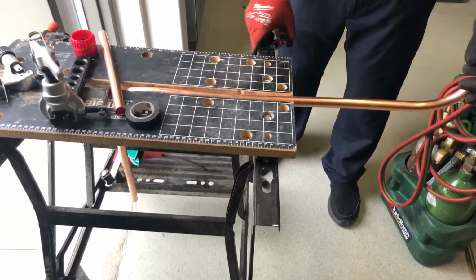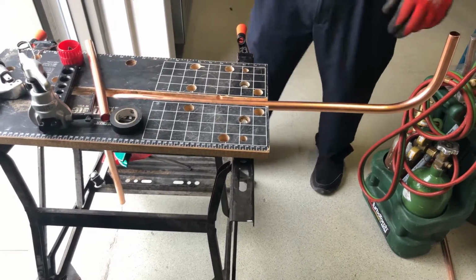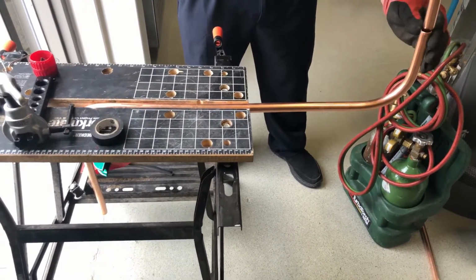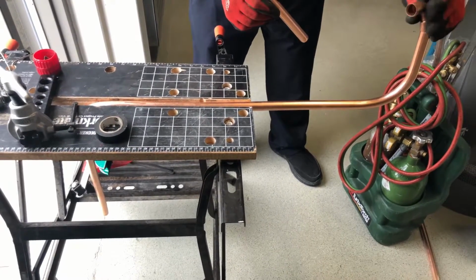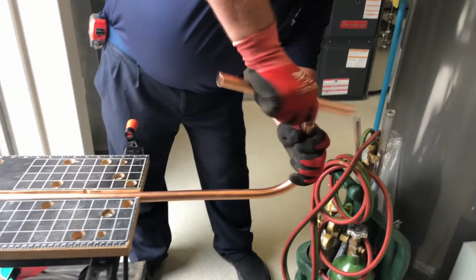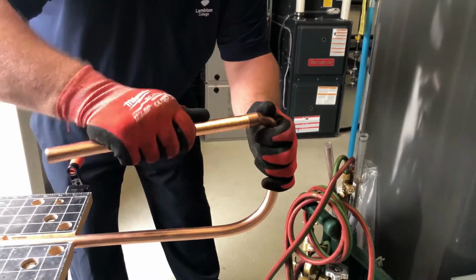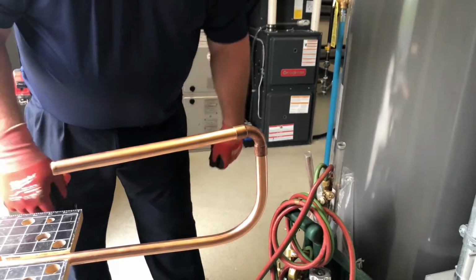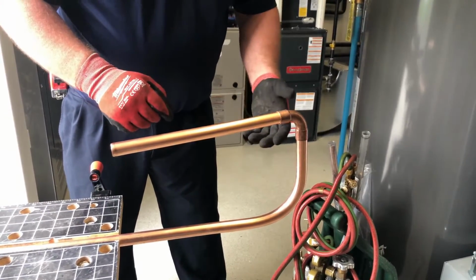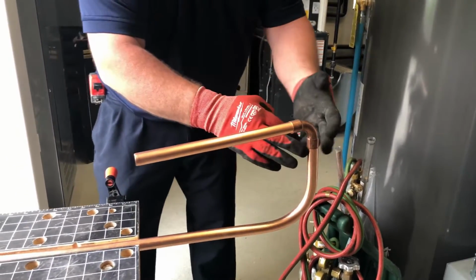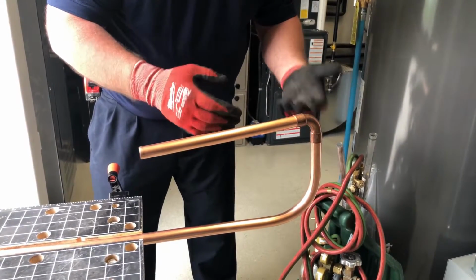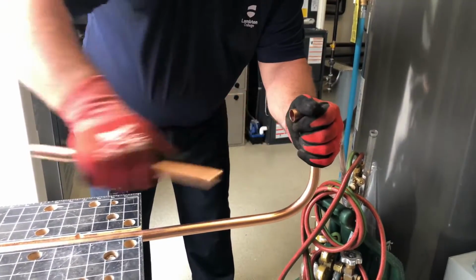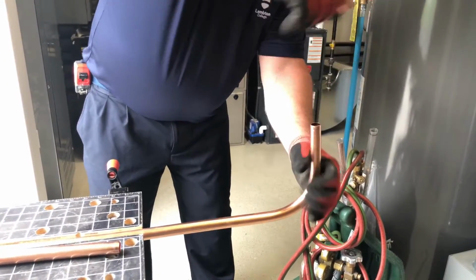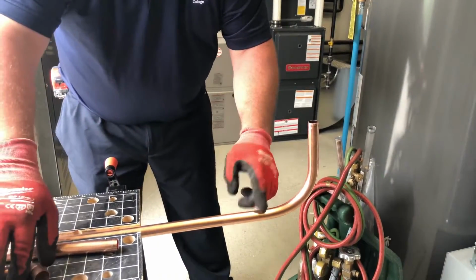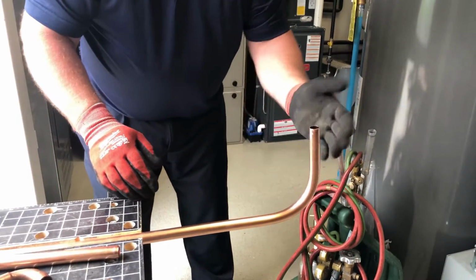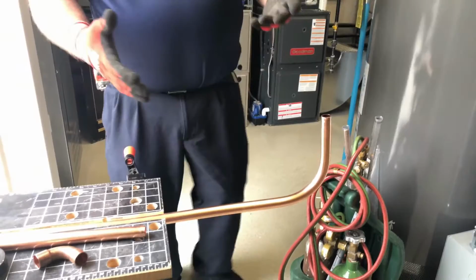Swedging is used a lot when joining two tubes together. We could use a fitting, like an elbow, and a lot of people are familiar with an elbow being used. I could put an elbow in there and braze that up, but the problem is we'd have two joints that could possibly leak. Whenever we can limit the number of joints, it's always a better process. So I could use my mechanical tube bender, like I just showed you, to bend a tube instead of having a joint, which should help prevent leakage in the future.